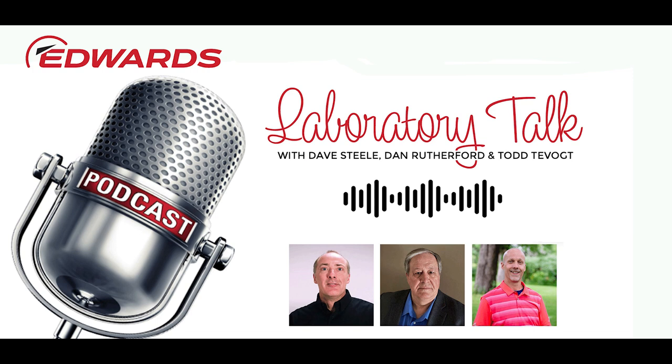Yeah. Each active gauge identifies itself to an active gauge controller. The controller then selects the appropriate conversion algorithm to interpret the gauge's output to a pressure reading, and it allows easy conversion between pressure units also. All right, so you can change between millibar, pascals, hectopascals, whatever you like quite easily just by putting a little algorithm into your processing. Exactly. And with the active gauges, this is one of the key advantages. The identification of each gauge head is a specific discrete resistor value that identifies the type of the gauge head to whatever control you plug it into. So it really is plug and play.